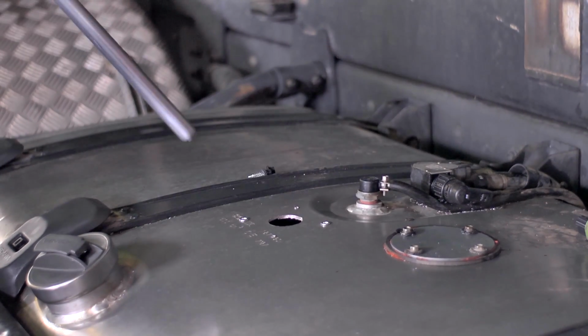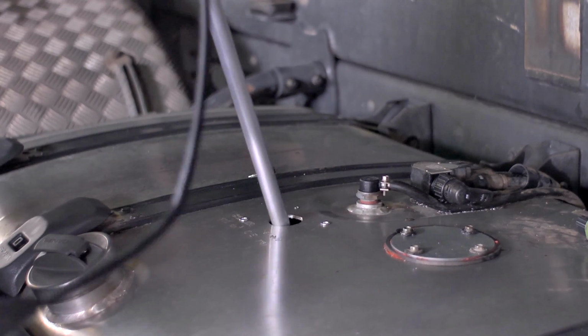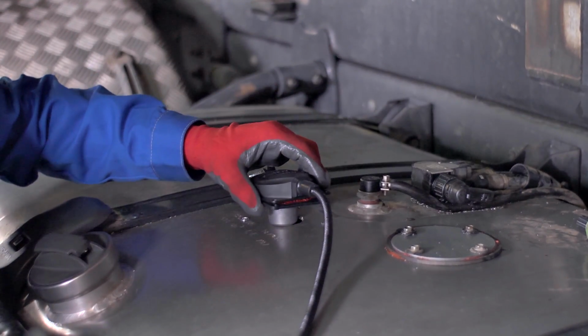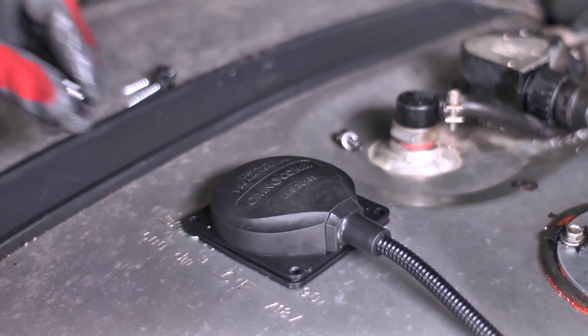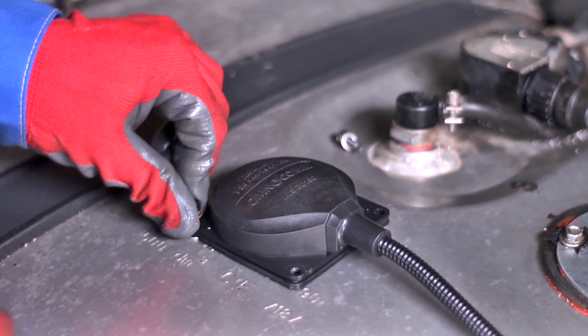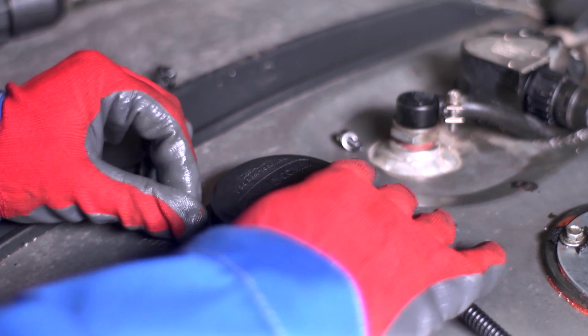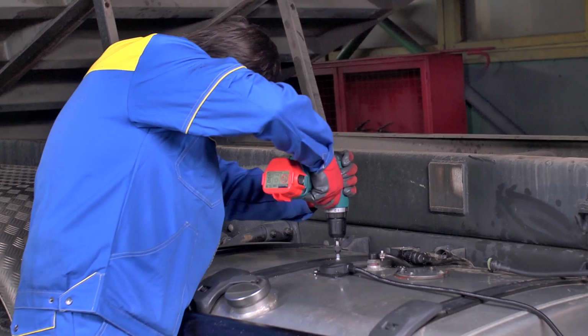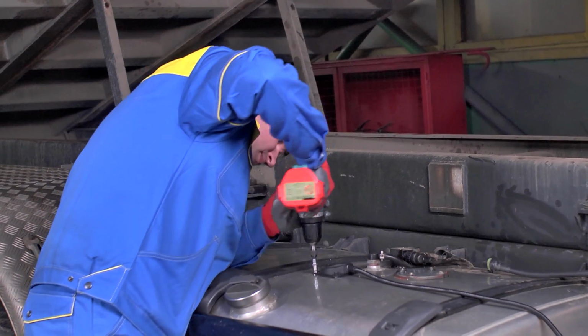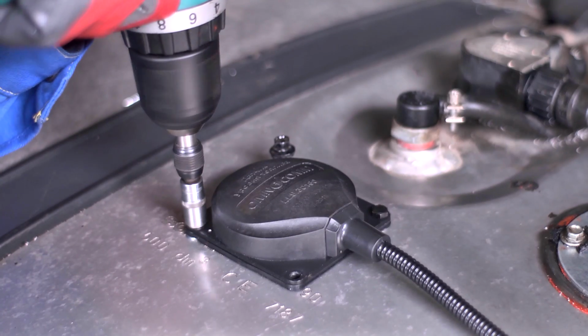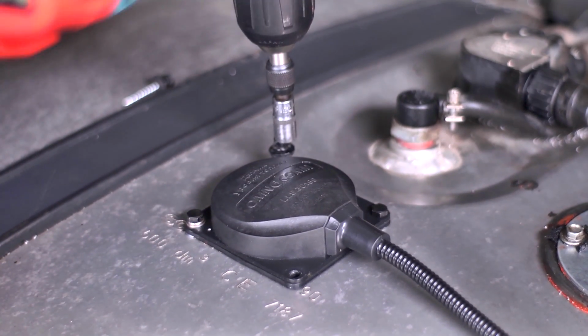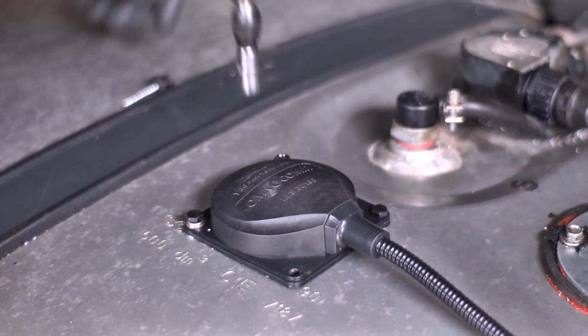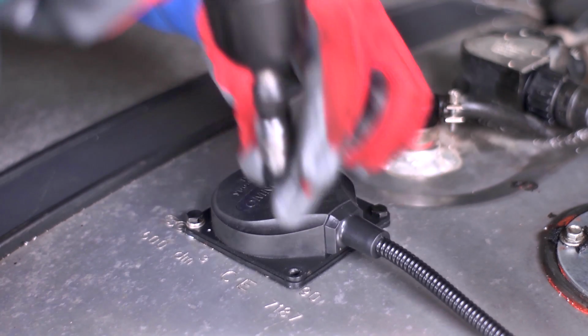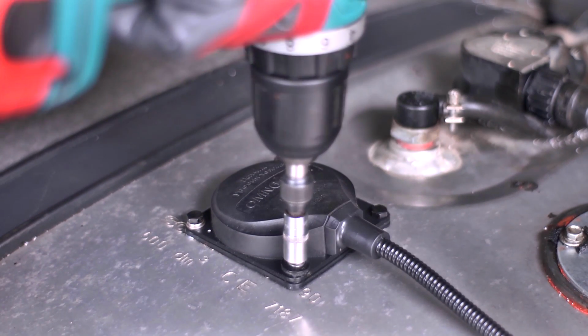Install the sensor with the gasket into the fuel tank and fasten it using the chosen method, using self-tapping screws or rivets. Omnicomm professionals recommend using rivets for tanks made from a metal having a thickness of less than 4 mm. Self-tapping screws can be used for tanks with a metal having a thickness of more than 4 mm. Now the sensor has been installed in the fuel tank and is ready for use.